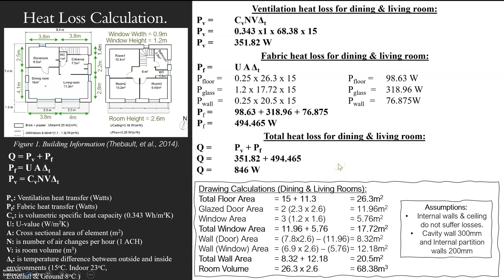A couple of things: I am making assumptions about internal walls and internal ceilings. Looking at this dining room and living room — upstairs I've got the same spaces above me, so I'm assuming the temperature above or below me is going to be comparable. I'm not going to work out heat losses through those internal spaces or the internal walls. The only time I'd worry about internal walls giving heat losses is if I had a garage, or if I had a cold storeroom kept really cold — then yes, I'd probably lose some heat into that space. But in this case, all internal spaces are excluded.